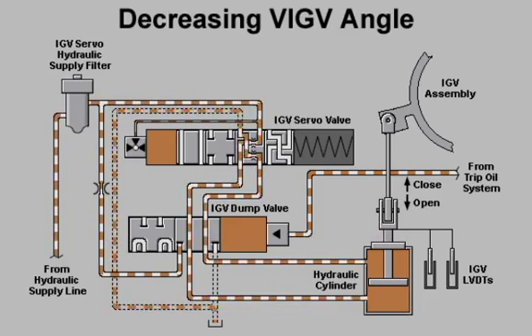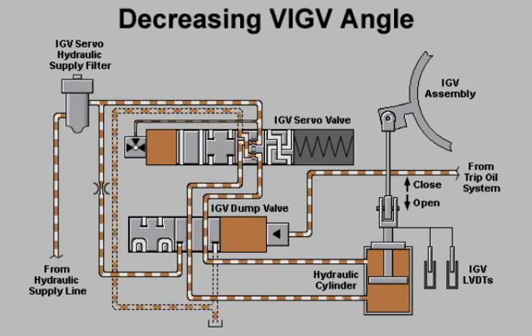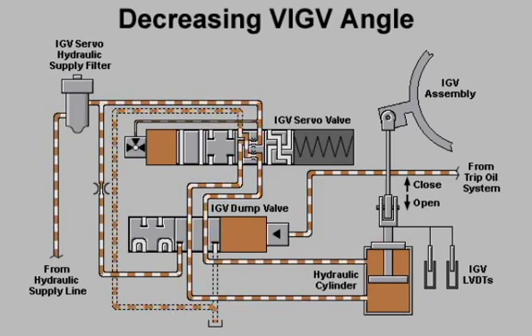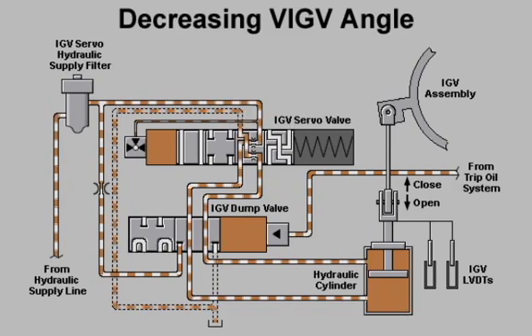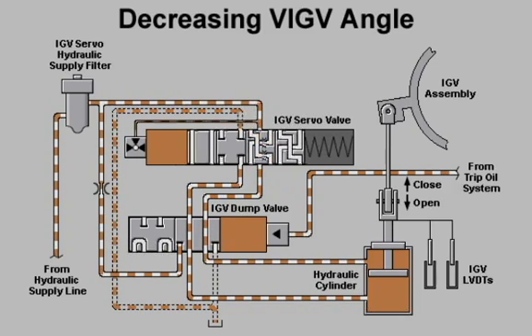The actuating arm of the hydraulic cylinder extends and rotates the inlet guide vane ring clockwise, turning the variable inlet guide vanes to a smaller angle.